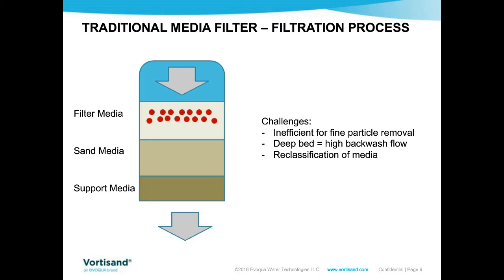The best filter actually is something that nature invented, and it's the beach. Beach sand is very fine, but of course, in order to filter an important quantity of water, you would require a very large surface area. So obviously, for practical purposes, and to avoid plugging of the media, we don't use a beach in our industry. We use media filters. The size of the media is coarser. The number of layers is increased also. It has a benefit. The filtration rates are pretty high. However, the efficiency to remove particles under 10 microns is not very good. So how do we compensate?